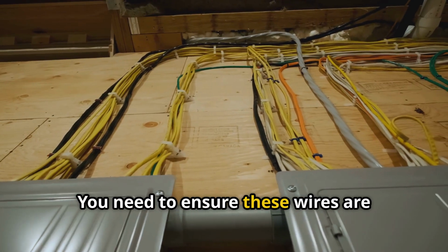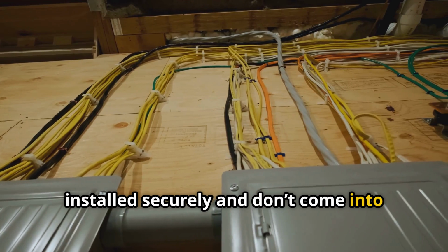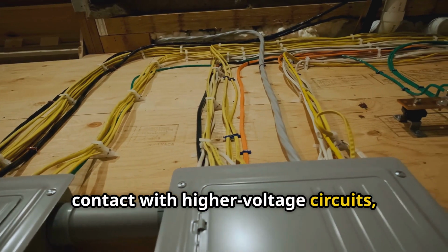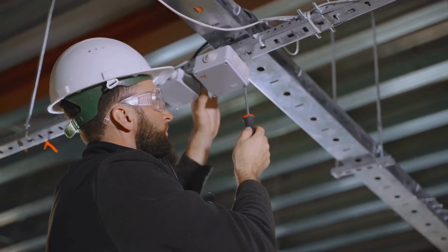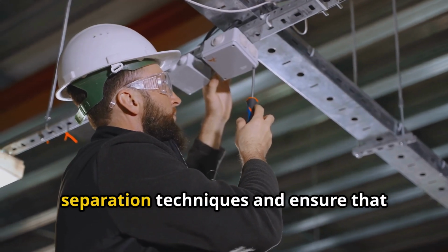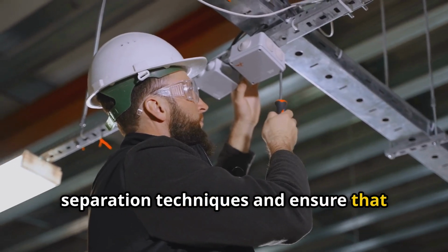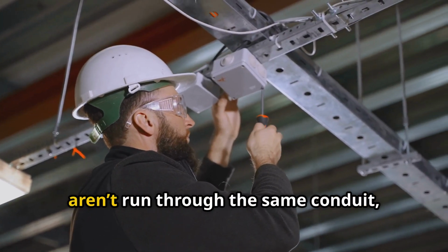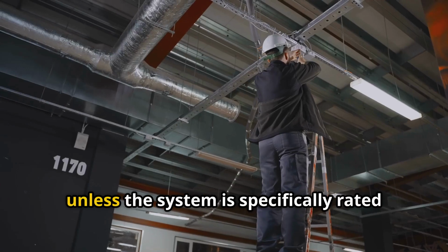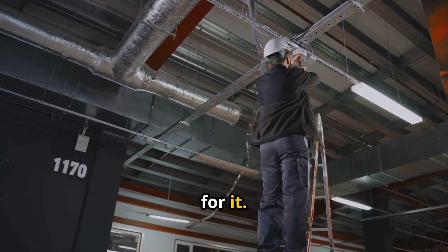You need to ensure these wires are installed securely and don't come into contact with higher voltage circuits, which could create a hazard. This means you need to use the correct separation techniques and ensure that low voltage and high voltage circuits aren't run through the same conduit unless the system is specifically rated for it.